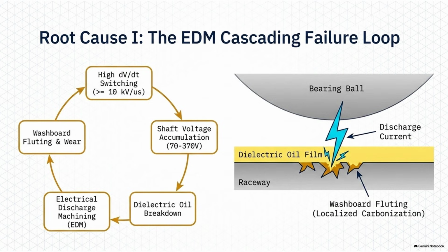And what about the steel? The sources say it leaves microcraters. Yeah, the plasma blasts tiny pieces of metal right off the glass-smooth steel raceway of the bearing. One spark leaves one microscopic crater. Right. But remember, the motor is spinning at maybe 10,000 RPM, and the inverter is switching thousands of times a second. So you are getting localized lightning strikes thousands of times a second. Yes. Over time, those tiny invisible craters start to overlap. You are essentially sandblasting the inside of a precision bearing. And those overlapping craters create a wave-like washboard pattern on the metal. Mechanical engineers call this fluting.